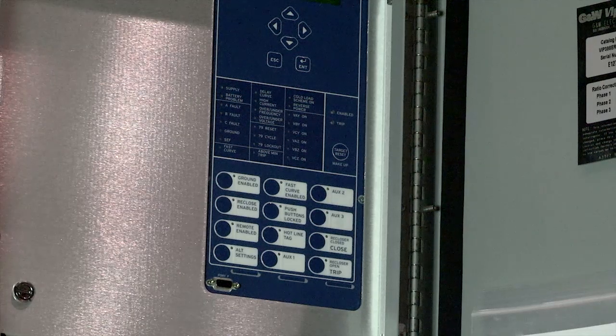So over here is just a shot of the 651R controller that controls the Viper reclosers. Now, I'm not going to get into too much detail about it. As far as the auxiliary buttons that are on this controller, we're able to actually set 6 different setting files per recloser. This comes in really handy with these mobile units, because we could have different setting files for each setting group. So as far as going to a station with high fault amps, low fault amps, long or short feeder ends, we're able to switch this with the push of a button, and have our reclosers now see its feeder end in less than 3 seconds. So this makes it very versatile and very easy to manipulate as far as moving from station to station.